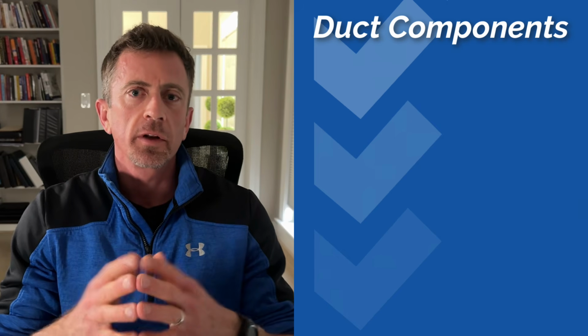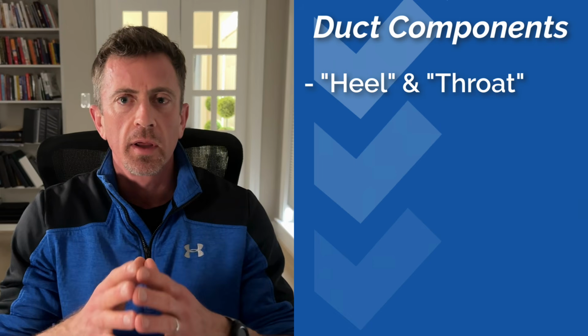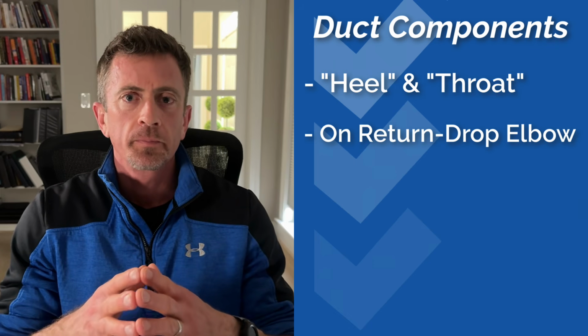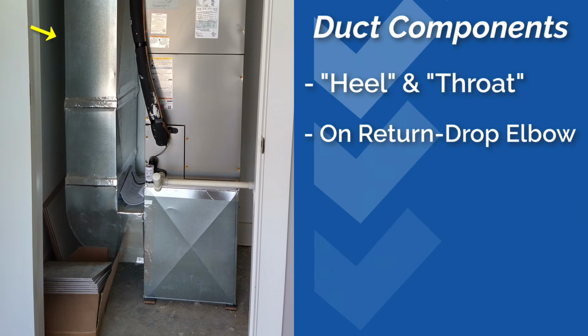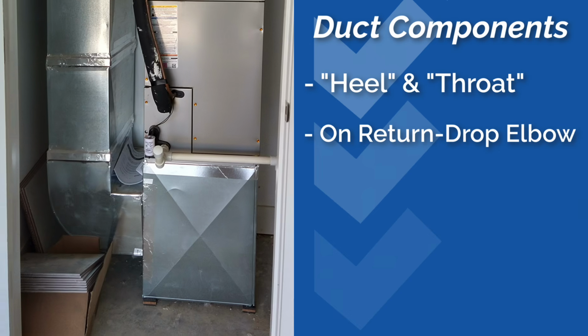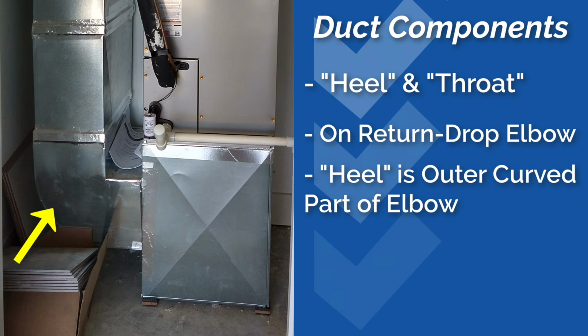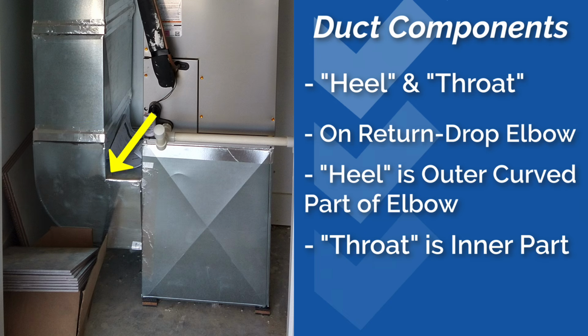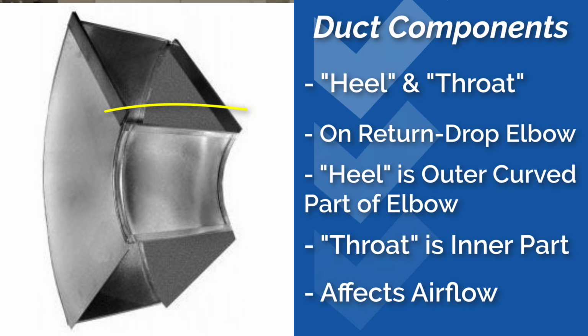The next couple things we're going to talk about are the heel and the throat as far as the return drop. So on a return drop, it comes down from the ceiling generally and makes a turn into the air filter rack and goes back into the system. And what's called the heel is the outer curved portion of that return air elbow. The throat on this is the inner tighter radius portion of the elbow, affecting airflow efficiency. Making these throats rounded can reduce static pressure and increase airflow through the system.